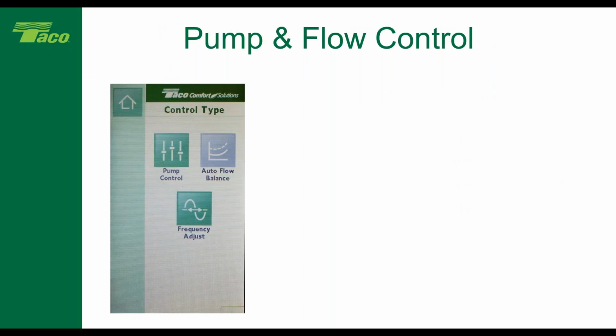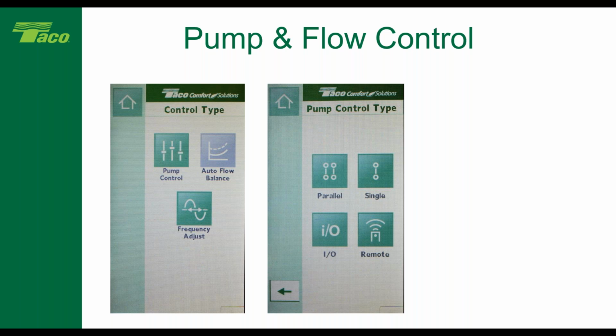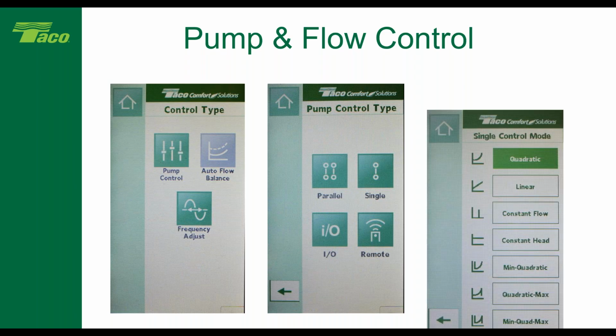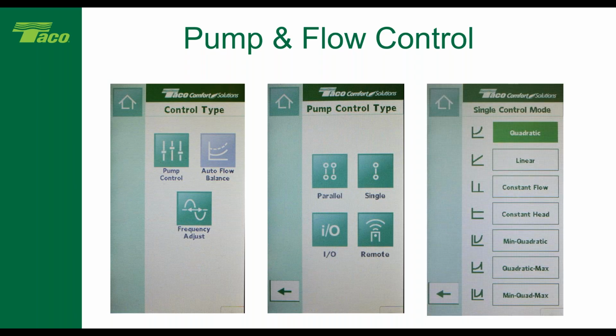So when we look at this, we've got different pump types. So we've got pump control, and you see another thing that says auto flow balance. We'll talk about that in a minute. And then you've got different pump control types, and most common is going to be parallel. Okay, so you're going to set up parallel pumping. When you set up parallel pumping, you've got different control modes that you can set up.